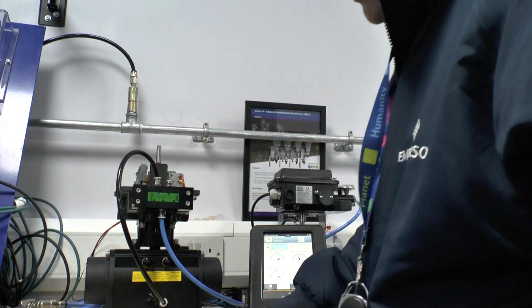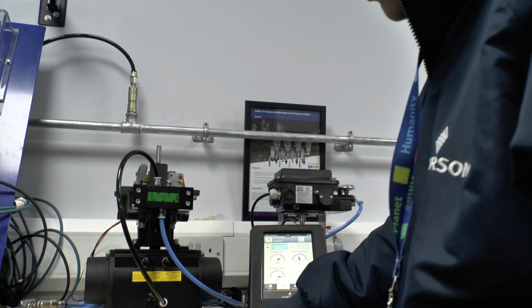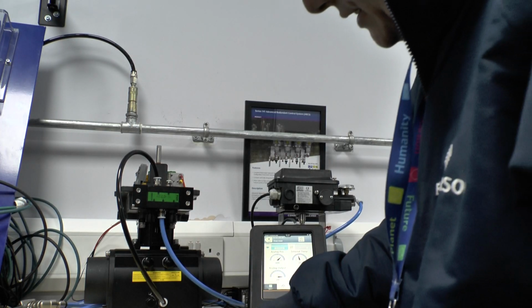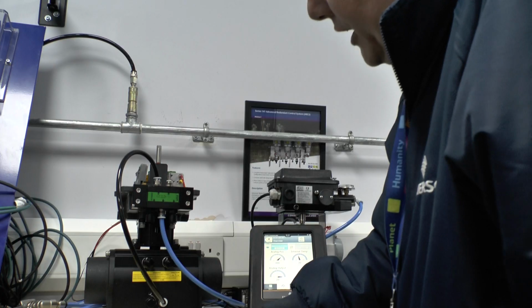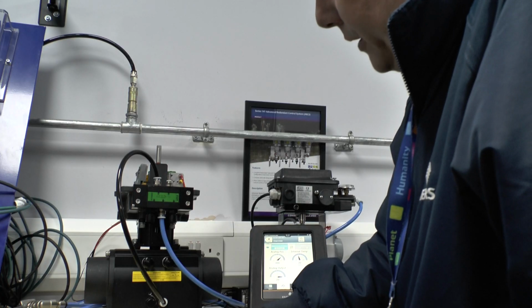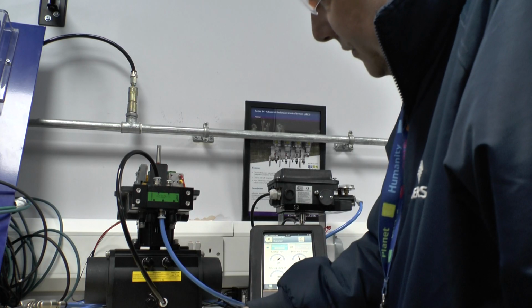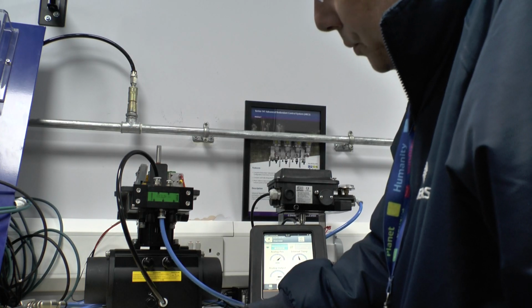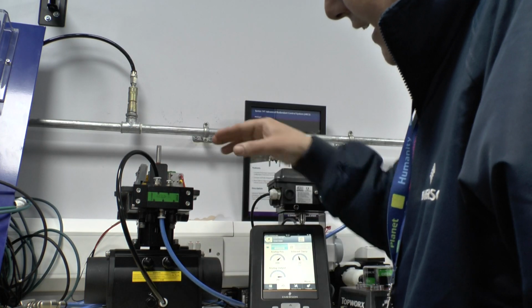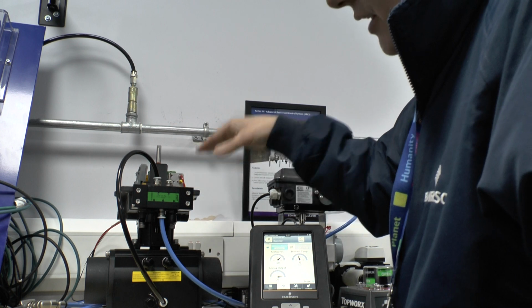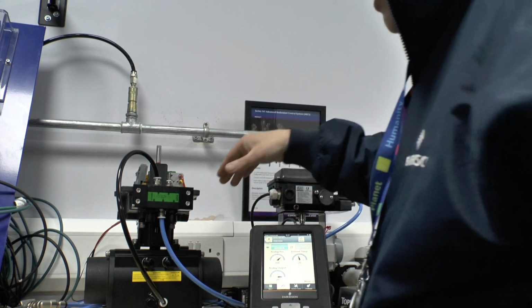Customers need these emergency shutdown valves to always be open or always closed. What you need to do is prove, over a period of time, that because that valve is always in the open or closed state, if it has to be enabled, it's actually moving - it comes off its seat, etc.